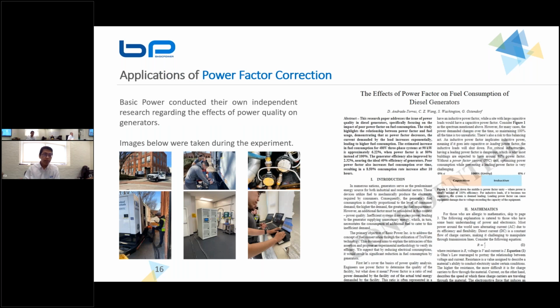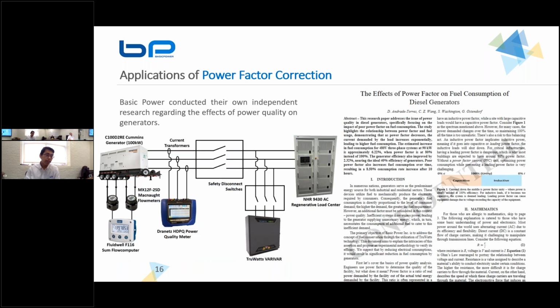Now, not only will this affect the actual utility companies, but if you have your own generator, if you're in a closed microgrid system, or you're powering from a local source, this can actually help reduce your amount of fuel consumed during your operation. We actually conducted our own white paper study where we had a generator and we had some flow sensors to measure the fuel consumed inside the generator. And by allowing us to change the power factor from being efficient to inefficient, we're able to detect the difference of how much fuel you consume. And as it turns out, there's roughly between 4 to 6% improvement in terms of fuel consumption during this operation of improving power factor.